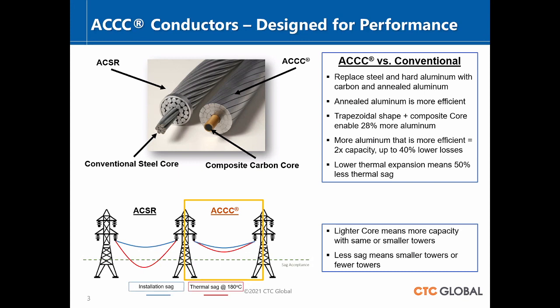You can put twice the power flow through here as you could with this and still not sag out of service. There's a brief example here that shows the traditional ACSR and the ACCC both operating at 180C. You wouldn't operate the ACSR there, you can see, because it would sag lower than its clearances allow, right? We'll comment on the operation of that in just a moment. So the value proposition for the ACCC advanced conductor is the capacity. You can put 2 times the flow through here and stay in service. You may not design it for that, but you can call on that and get that service out of this conductor.